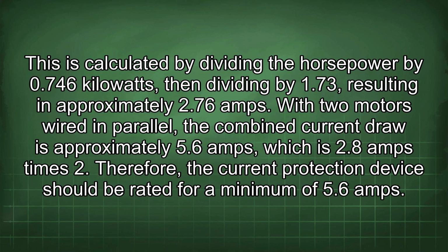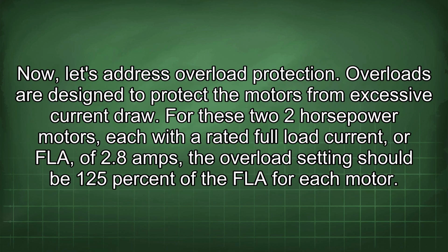With two motors wired in parallel, the combined current draw is approximately 5.6 amps, which is 2.8 amps times 2. Therefore, the current protection device should be rated for a minimum of 5.6 amps. Now let's address overload protection. Overloads are designed to protect the motors from excessive current draw.